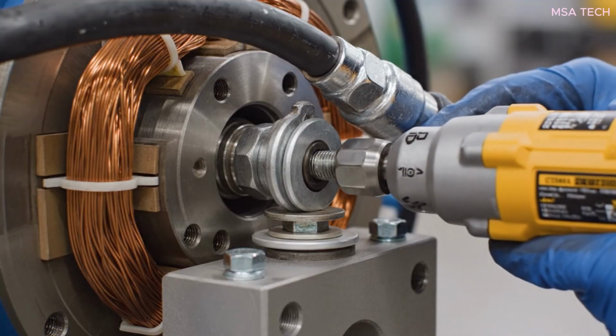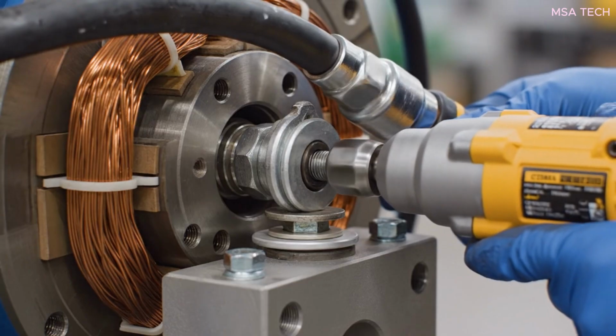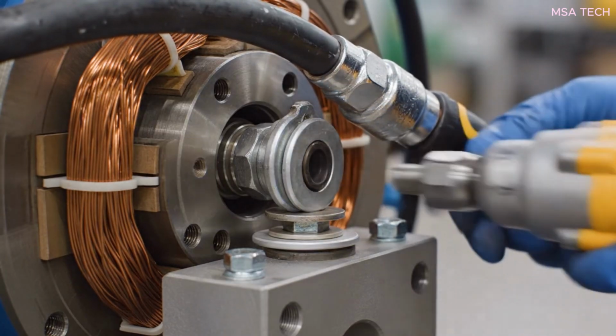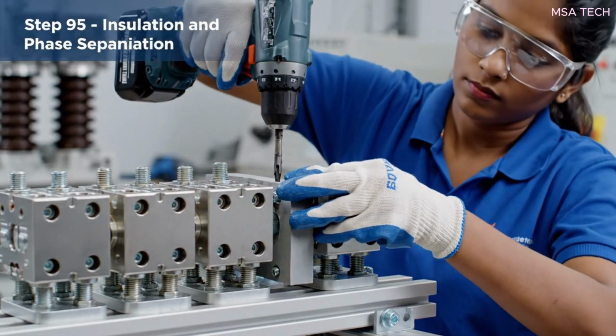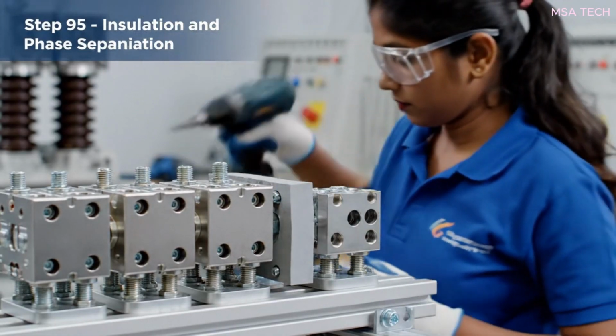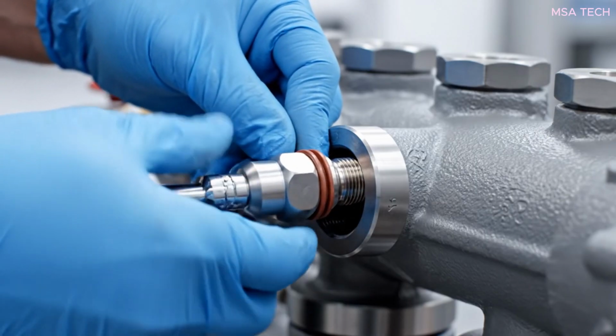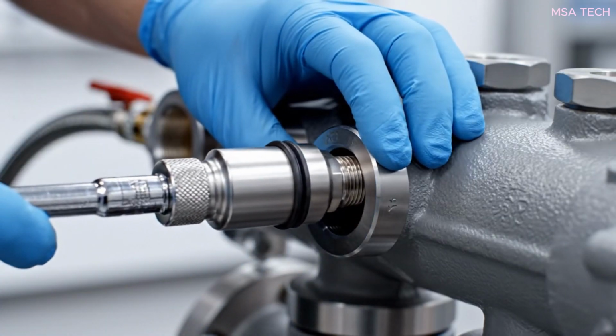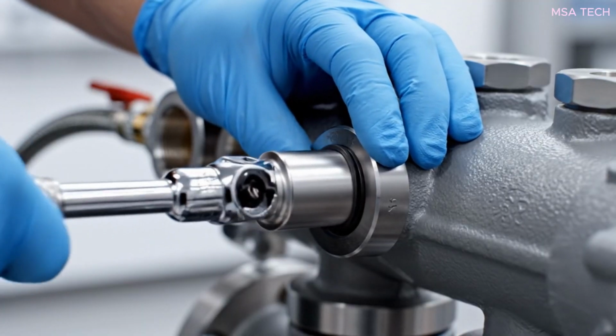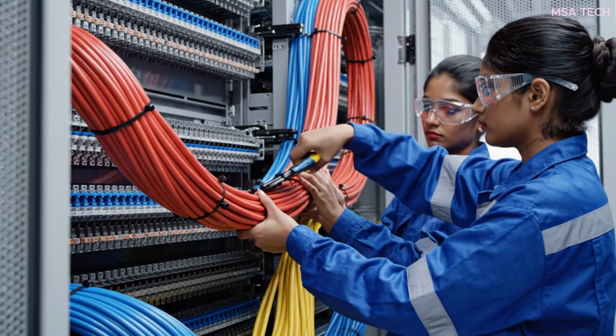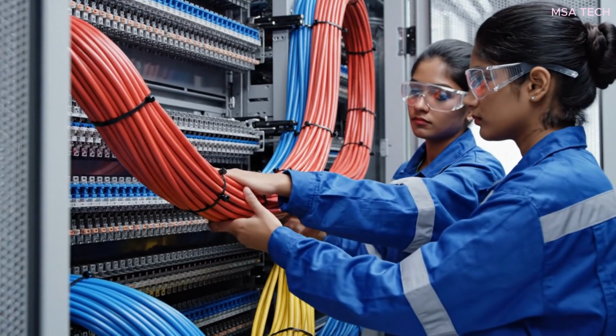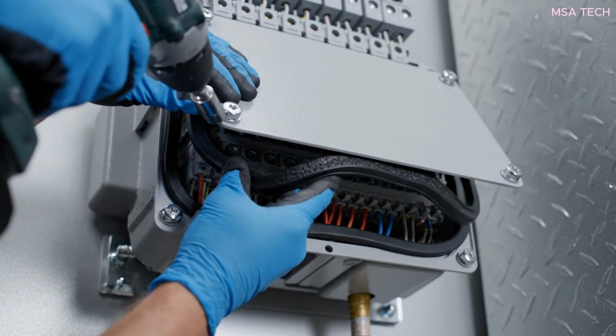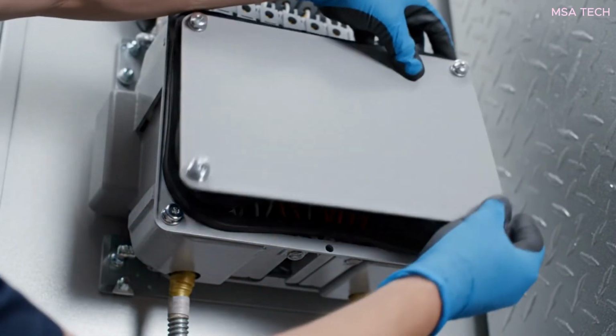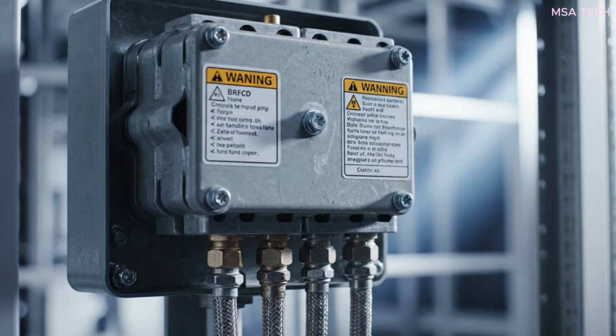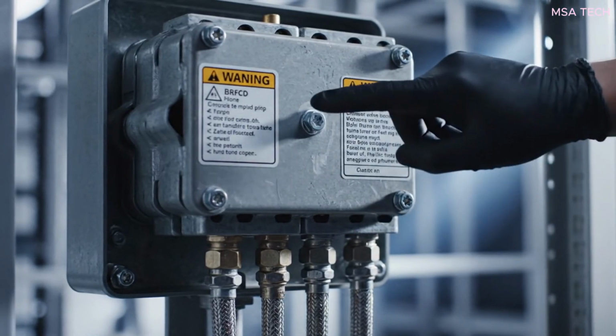For step 94, ensure the power cables are securely bolted to the stator terminals using the torque tool, verifying correct lug seating and washer alignment. Temperature sensors, vibration pickups, and RTDs are installed into designated ports, with careful thread engagement and seal placement. In this step, we install the terminal box cover and tighten the fasteners in sequence to ensure proper gasket compression and sealing. Proper electrical termination is critical. It ensures both safe power delivery and long-term operational reliability.